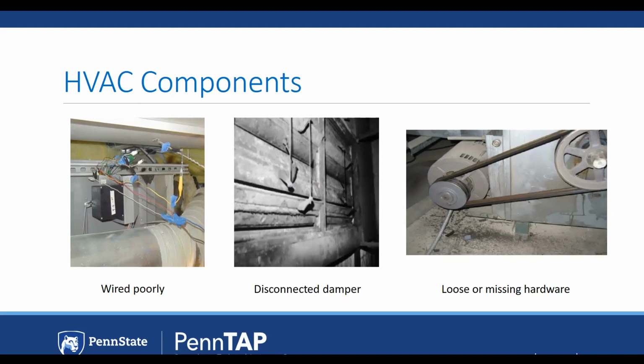Common problems in HVAC systems can include jammed or frozen outdoor air dampers, missing or damaged panels, seals, ductwork, non-functioning actuators or disconnected wires, malfunctioning outdoor air or return air temperature sensors, faulty control settings, and equipment installed wrong or wired incorrectly. Also consider your equipment's coding as part of the install. Also, look for debris in the coils or the lines. Look for foreign material around the rotating equipment. Look for debris in the fan wheel or fan section. Look for insulation that has come loose, is hanging, or is falling down inside the housing or ductwork. Check for signs of belt debris or if the belts are failing. Also look for loose screws and/or bolts.